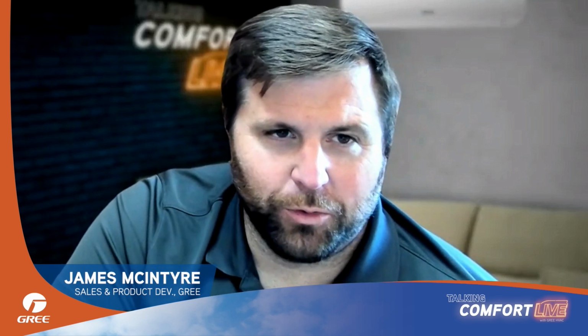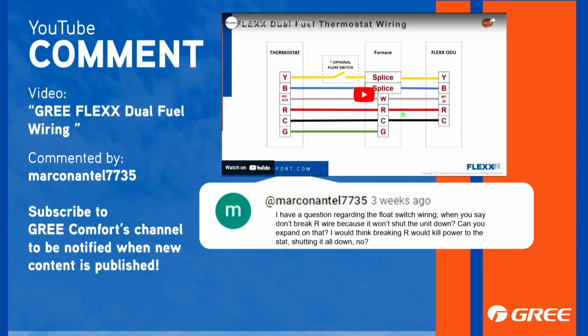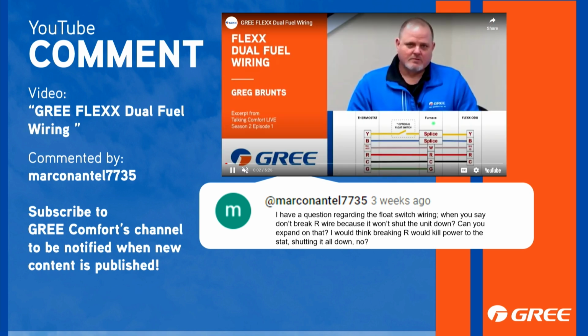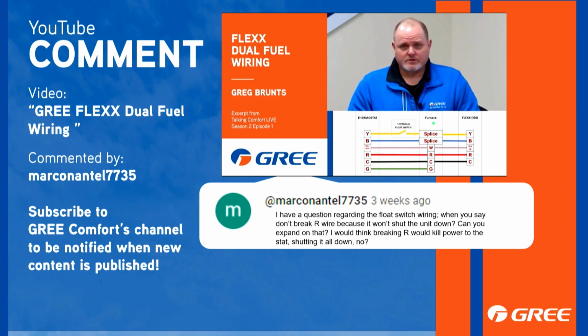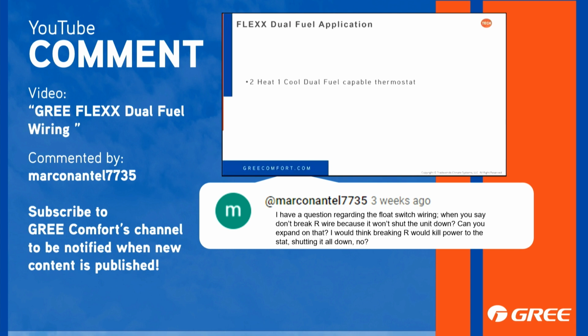On the FLEXX dual fuel wiring video, Marco asks: I have a question regarding the float switch wiring. When you say don't break R wire because it won't shut the unit down, can you expand on that? I would think breaking R would kill power to the stat, shutting it all down, no? That's a good question, a fair one. It depends on where you're breaking R. I guess I didn't clarify it well enough. What I meant was do not break R to the outdoor unit. If you break R to the outdoor unit, the unit will not shut down. But yes, if you break R to the thermostat, you're obviously going to lose your call and the unit will shut down. The easiest way to train it is just break Y, so we don't end up with the unit continuing to run and continuing to produce water.